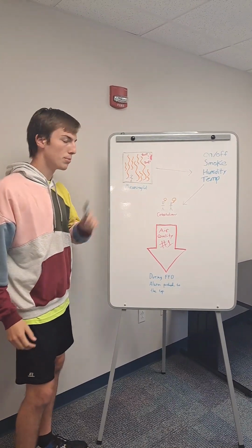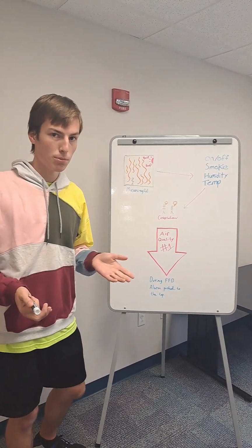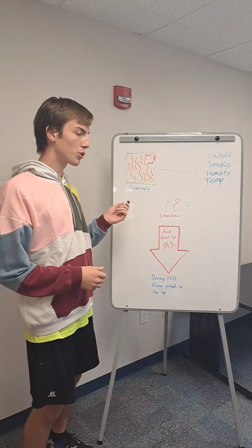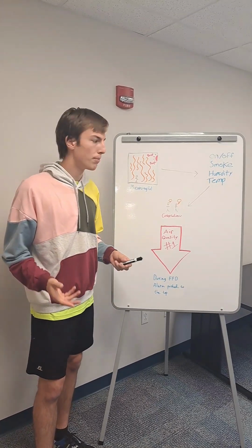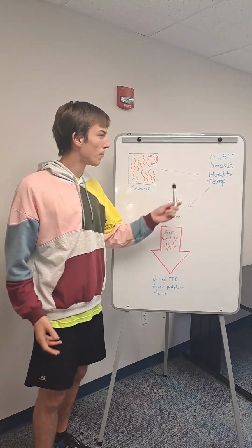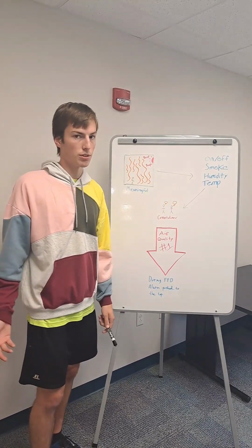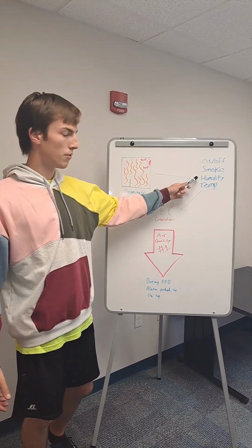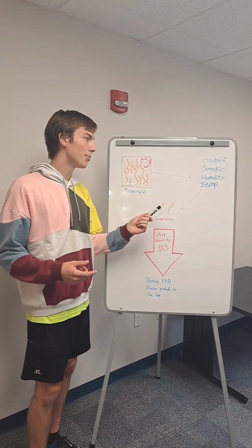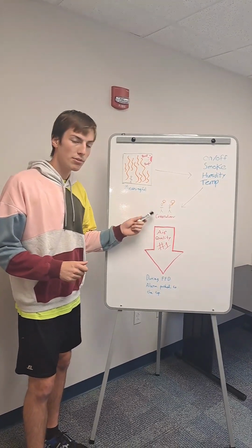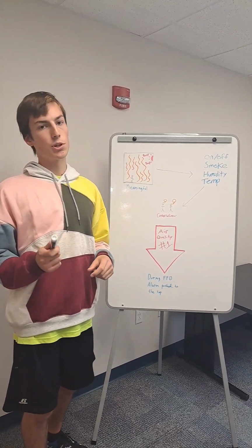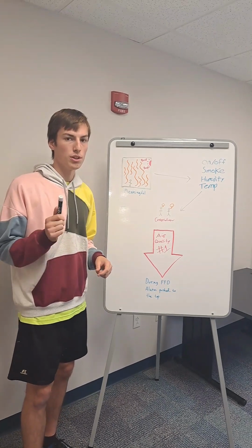Well, if you're in an office building and it's just too hot, people complain all the time. So when the alarms are going off, everyone ignores them. How do you know it's an important alarm? Well, smoke alarms, obviously. If there's a fire, you need to evacuate. For some buildings, it's humidity. For other buildings, it's temperature. You have to have a conversation with your customers to figure out what alarms are important to them.